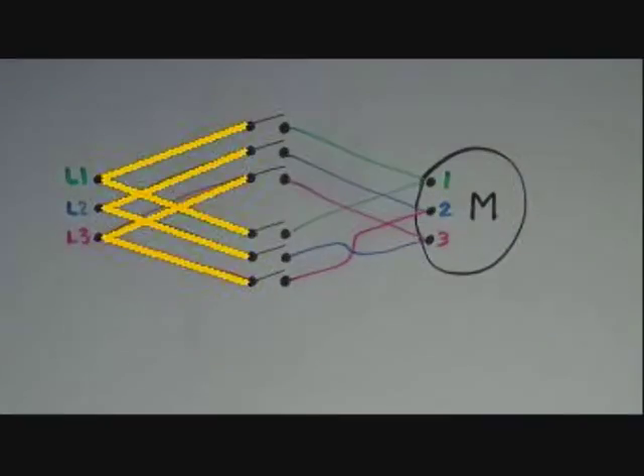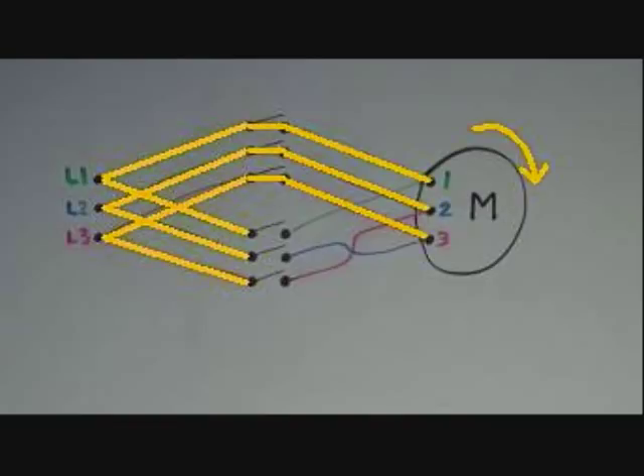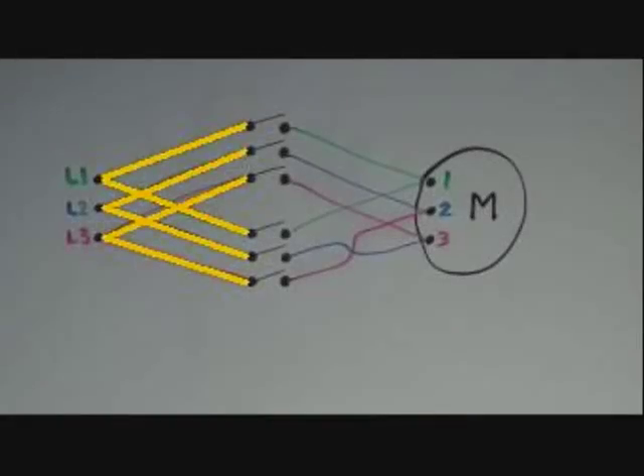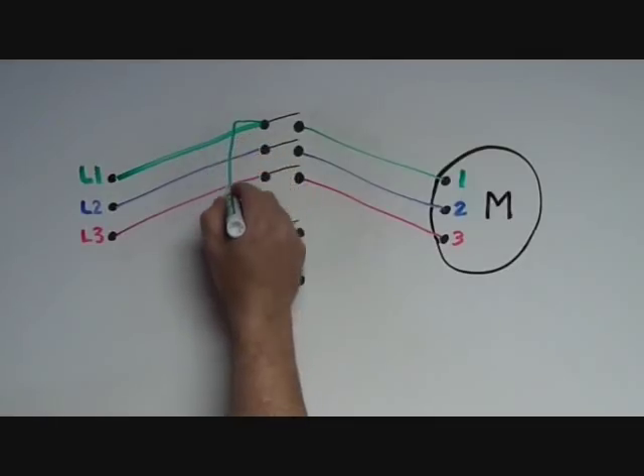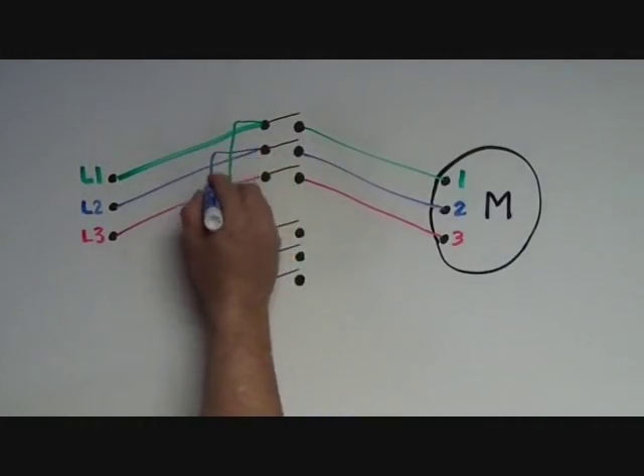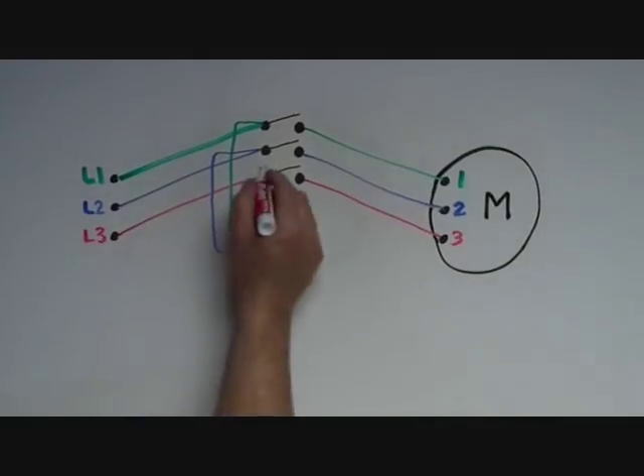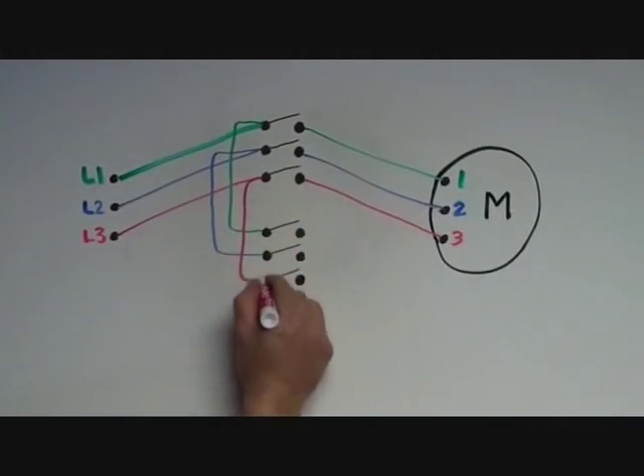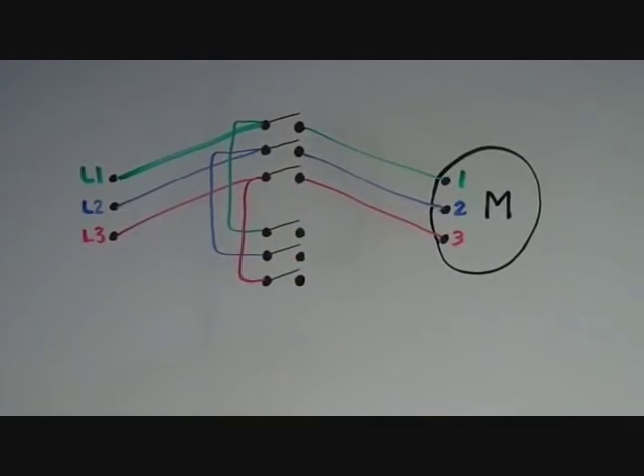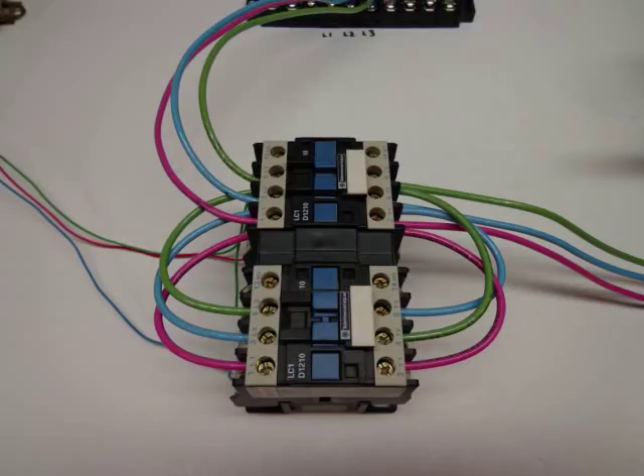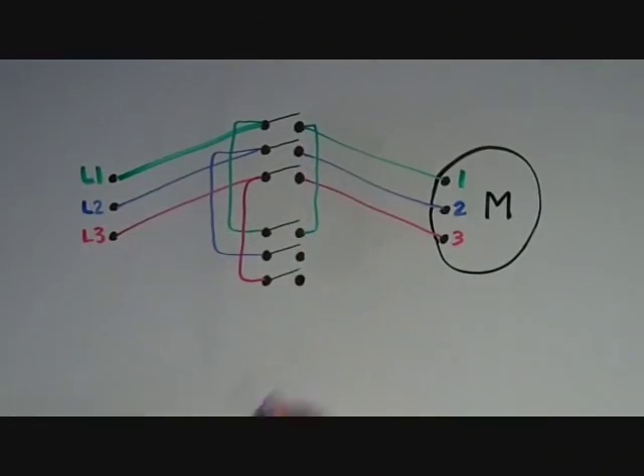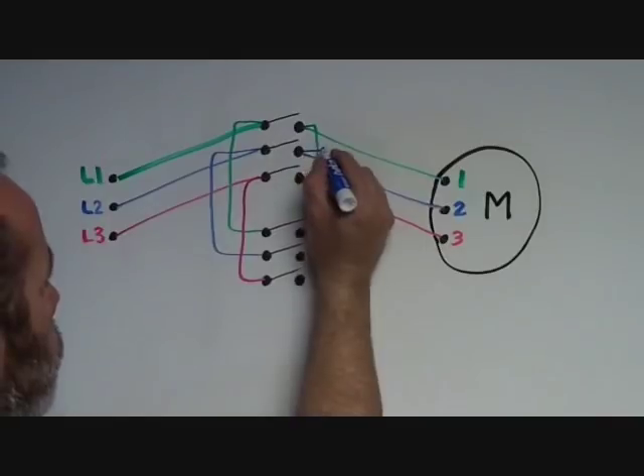So there's always voltage present at the line side of each contactor, but you can only operate one contactor at a time. So whichever set of contacts you close will determine the path of the current to the motor and the direction it spins. Since there's always constant power coming into the line side of the first contactor, I just ran jumpers from those terminals to the line terminals on the second contactor. This takes up a lot less wire than going all the way back to the three phase power source. And again on the load side, instead of running wire all the way to the motor, which might be 20 feet away from the contactor, I'll just run jumpers from the load terminals on the first contactor.